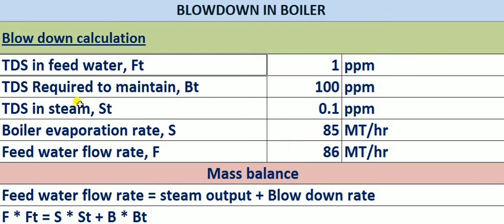Now, how to calculate the blowdown? The parameters required are: TDS measured in the feed water analysis — in our field it is 1 ppm, which is good quality water. We consider a 50 kg/cm² steam drum operating pressure. As per the vendor recommendation we maintain 100 ppm TDS in the boiler water; as per the standard we can maintain up to 150, 200, or 250 ppm, but for better efficient operation we consider 100 ppm.